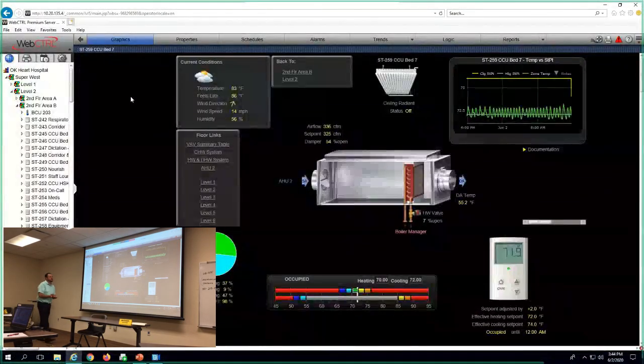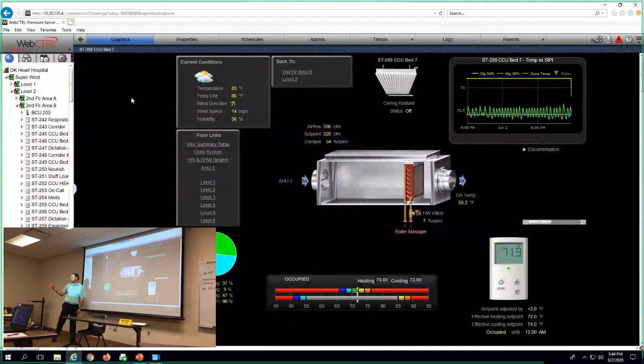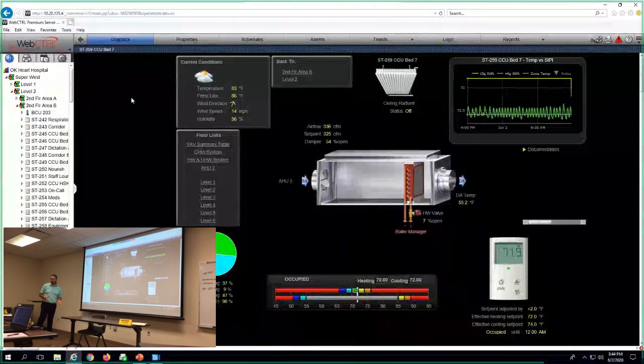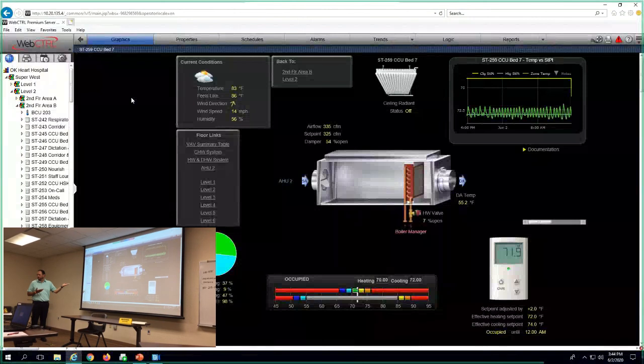So here's the biggest thing. Remember when I was talking about CFM? Almost always, we've got a problem and the air handling unit's doing what it's supposed to. You've got a good discharge temperature coming out of the VAV box. Do you have the airflow?